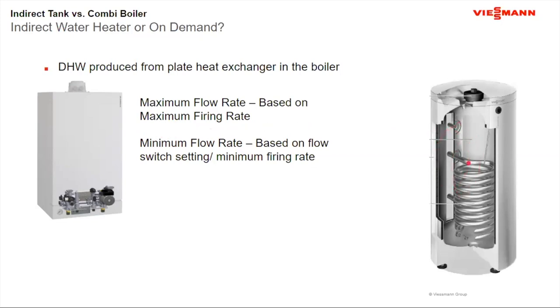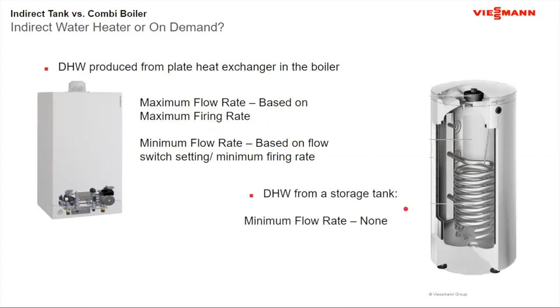Let's call it a 42-gallon tank, okay? Now, from this 42-gallon storage tank, I have water to draw against, so there is no minimum flow rate required because I'm not firing the boiler. I'm drawing against the volume of that water heater. Additionally, because I don't have a maximum flow rate that I have to worry about, there really isn't a maximum flow rate associated with the water heater.